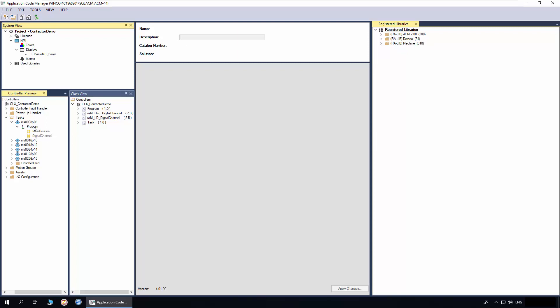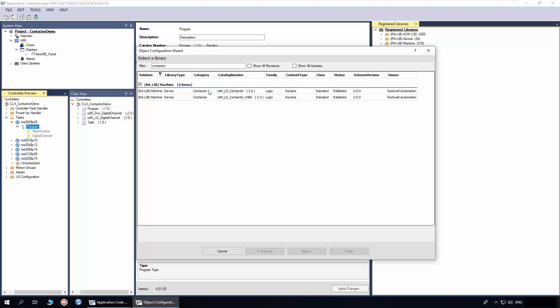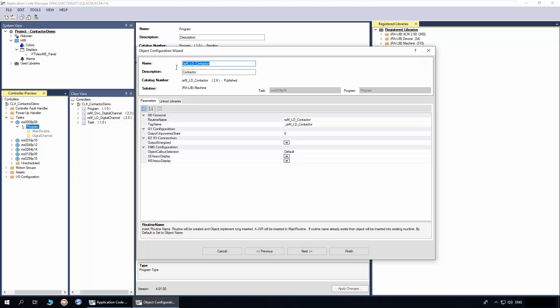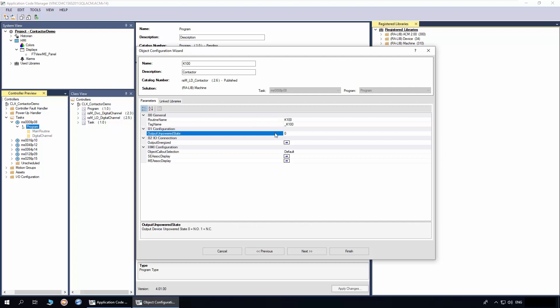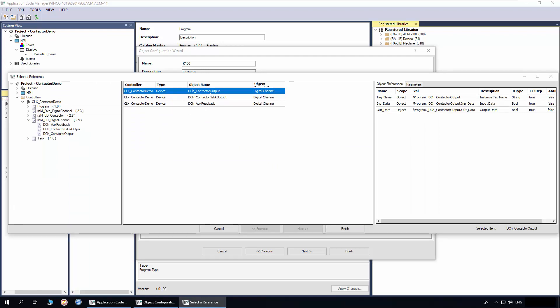To add a contactor, right-click on the program and click Add New. In the filter, enter contactor. Select the contactor implement object and click Next. I will enter the object name as K100. The routine and tag name are derived from the object name — you can modify or leave it as is. This is the unpowered state configuration; I will leave it as normally opened. In the I/O connection, you can link the object to a digital channel, digital output module, or enter a tag name. For this demo, I will select the digital channel already added in the project. I will select the DCI_ContactorOutput digital channel and select the input data reference. Click Finish.